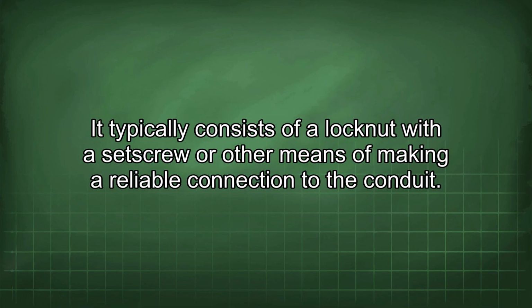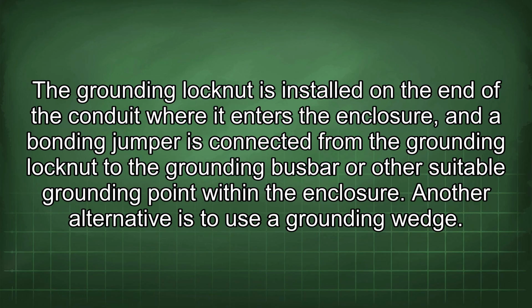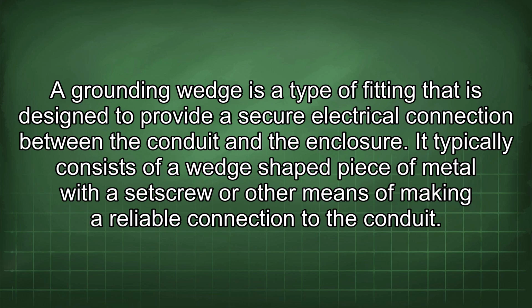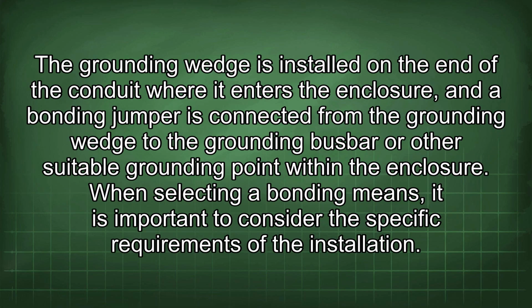It typically consists of a lock nut with a set screw or other means of making a reliable connection to the conduit. The grounding lock nut is installed on the end of the conduit where it enters the enclosure, and a bonding jumper is connected from the grounding lock nut to the grounding busbar or other suitable grounding point within the enclosure. Another alternative is to use a grounding wedge. A grounding wedge is a type of fitting that is designed to provide a secure electrical connection between the conduit and the enclosure. It typically consists of a wedge-shaped piece of metal with a set screw or other means of making a reliable connection to the conduit. The grounding wedge is installed on the end of the conduit where it enters the enclosure, and a bonding jumper is connected from the grounding wedge to the grounding busbar or other suitable grounding point within the enclosure.